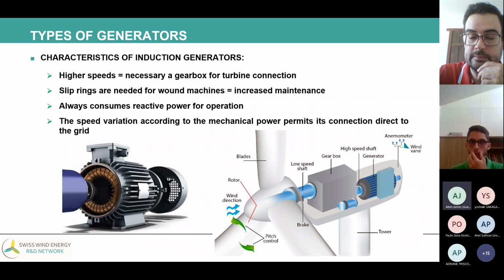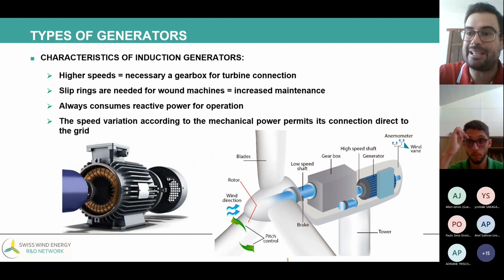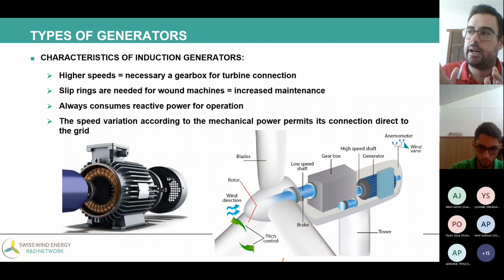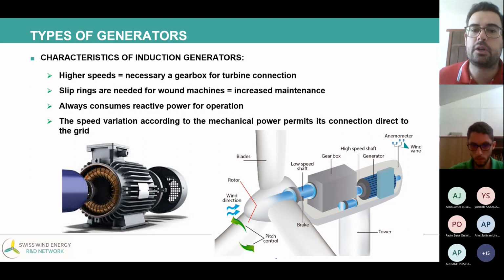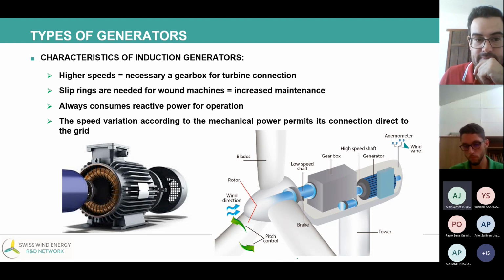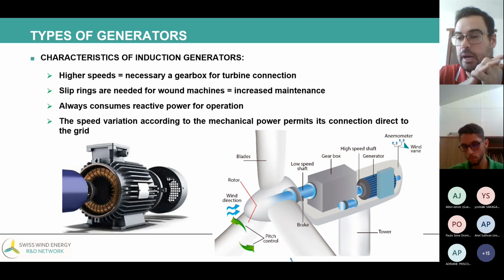So is the reactive power being supplied by the wind turbine itself? No. The reactive power is supplied by the grid, not by the turbine, because it's not energy. Okay? This is a good question. And what's the problem of consuming reactive power? The grid has to supply this reactive power for the operation of the generator. And this can be a problem for the grid. It's not a problem, but we can see it as a drawback for the grid. Clear, Alvin? Yeah, it's clear. Thank you. More questions about the generator part?